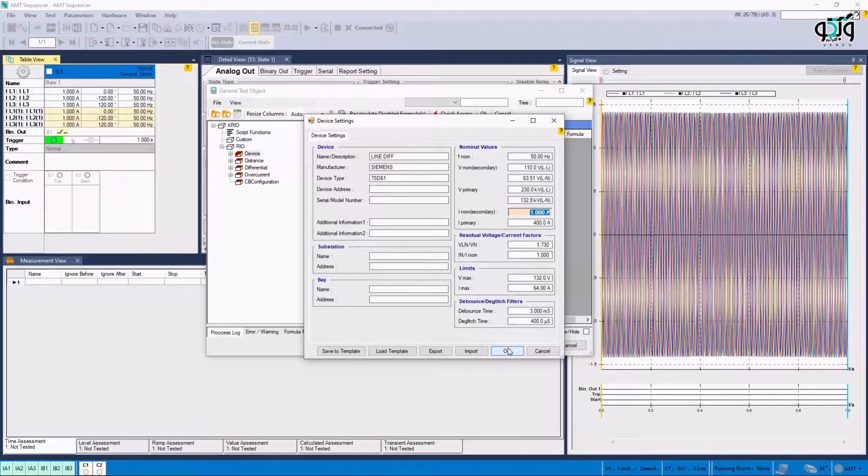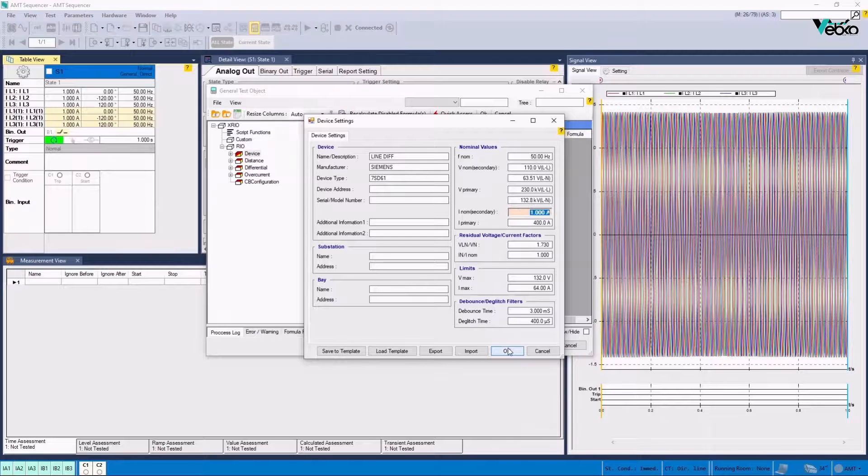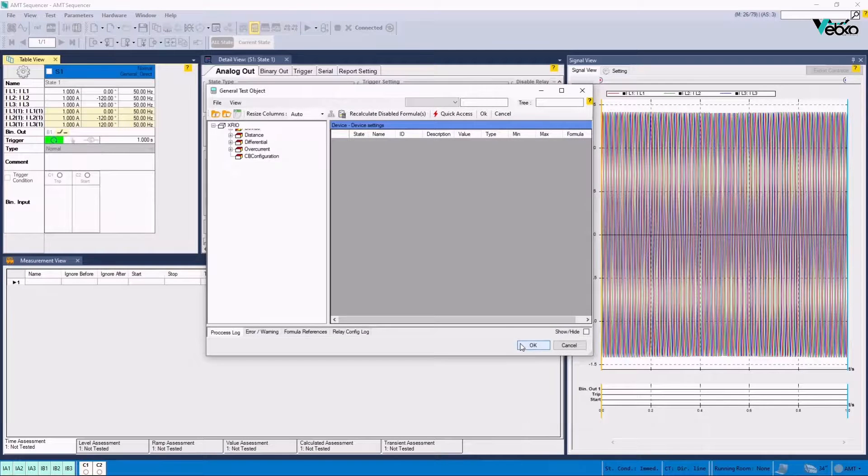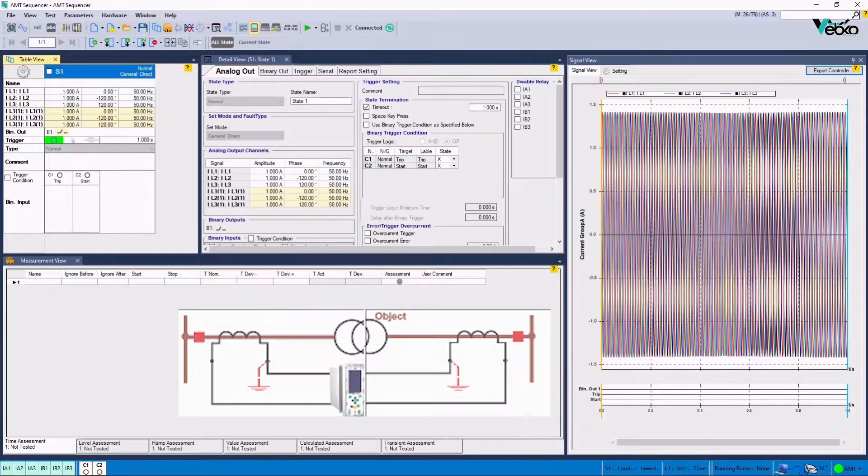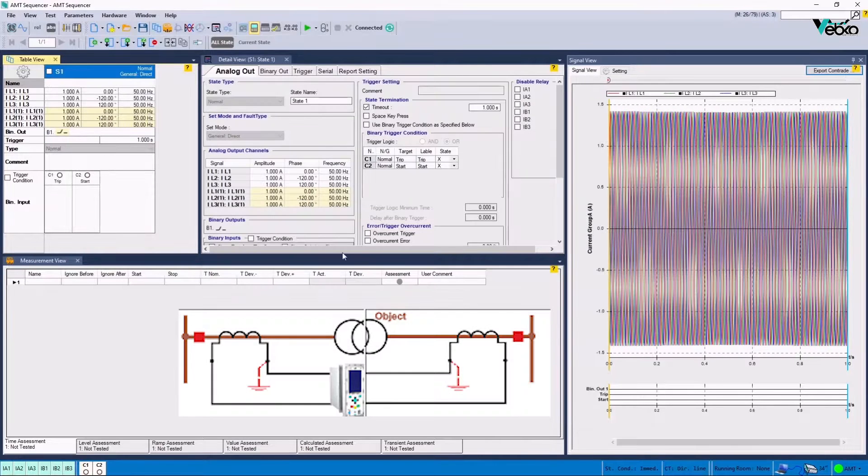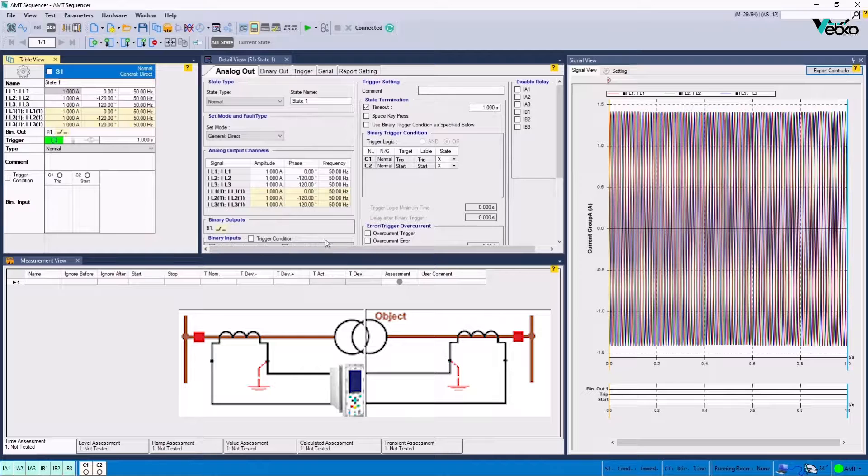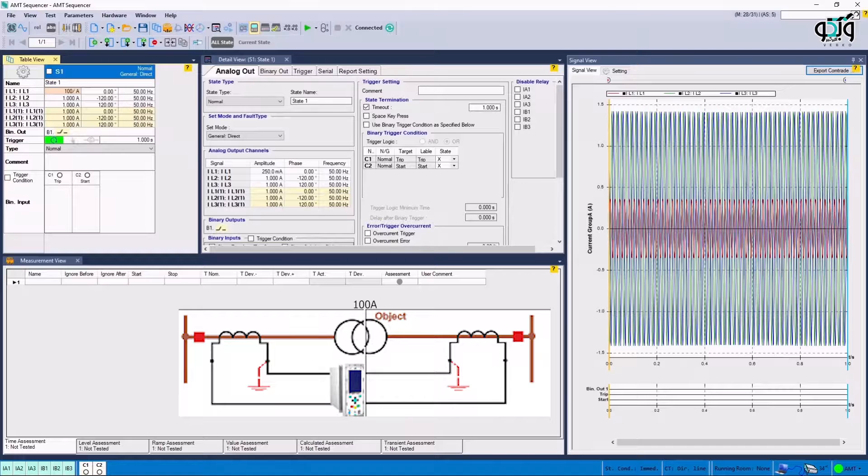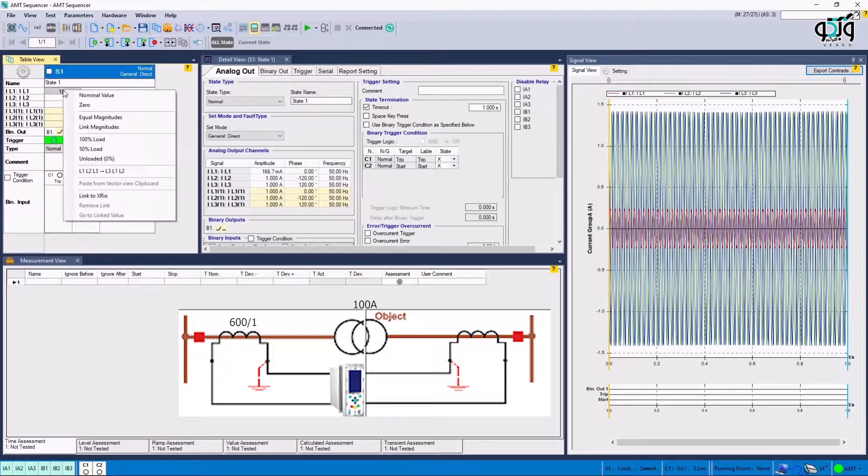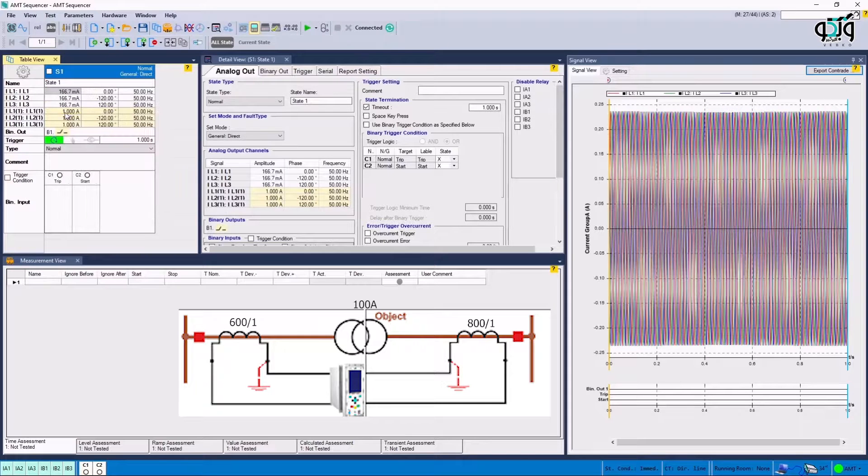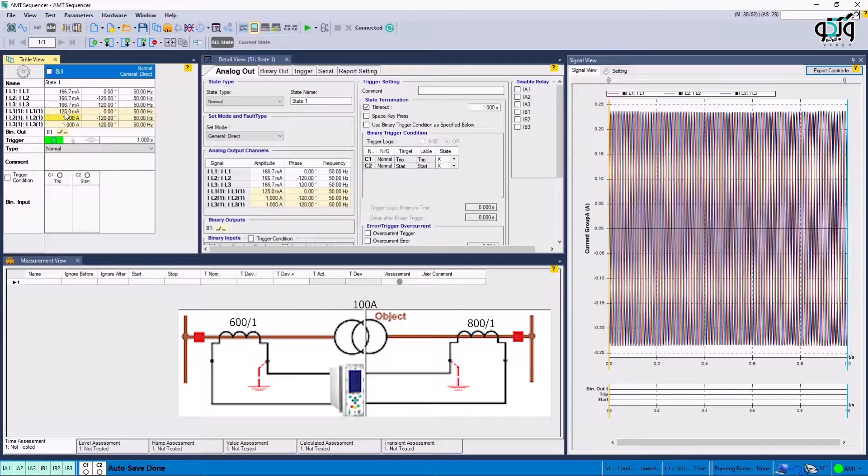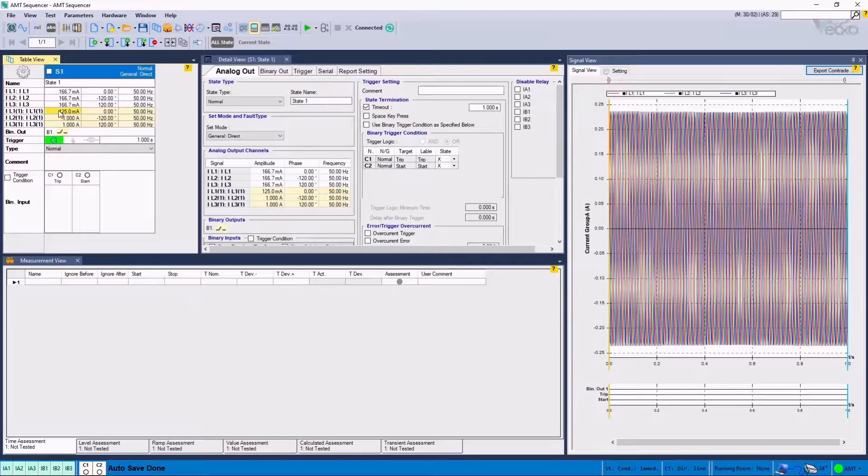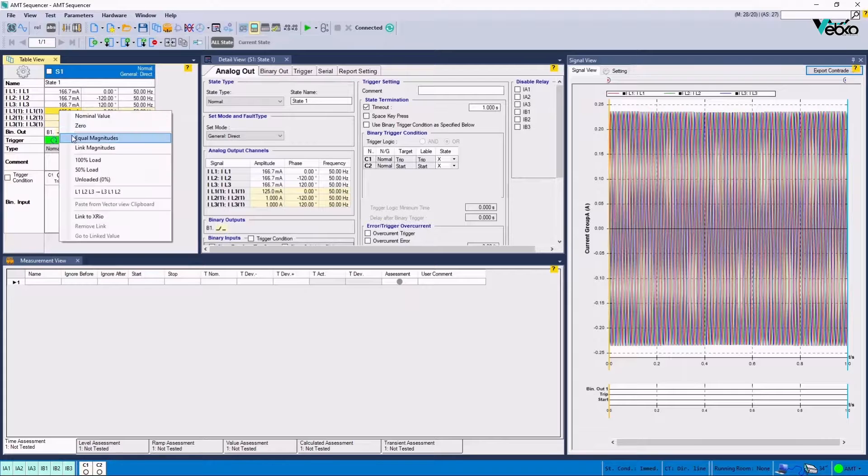In next step, the current value is to be entered in accordance with the differential settings as well as the turns ratio and CT polarity of the sides. For example, suppose that the line current is 100 amperes and the CT conversion ratio of the primary side is 600 to 1 while the turn ratio of the other side is 800 to 1 and the polarity is set at Toward Protected Object for both sides.